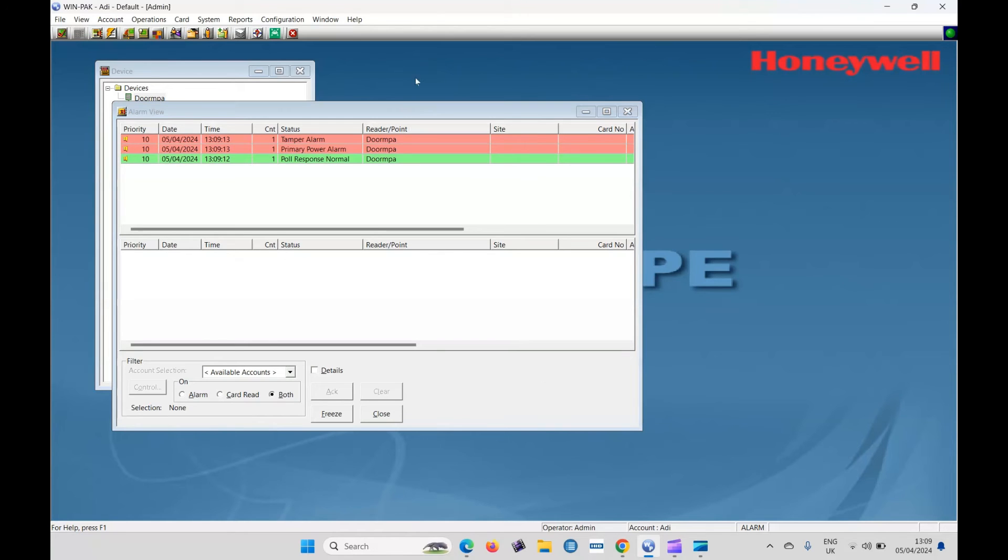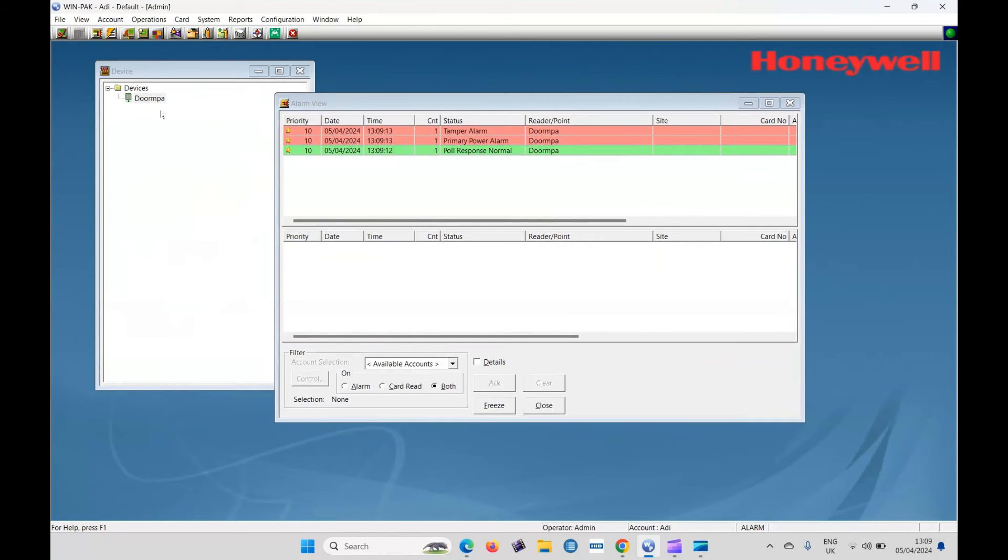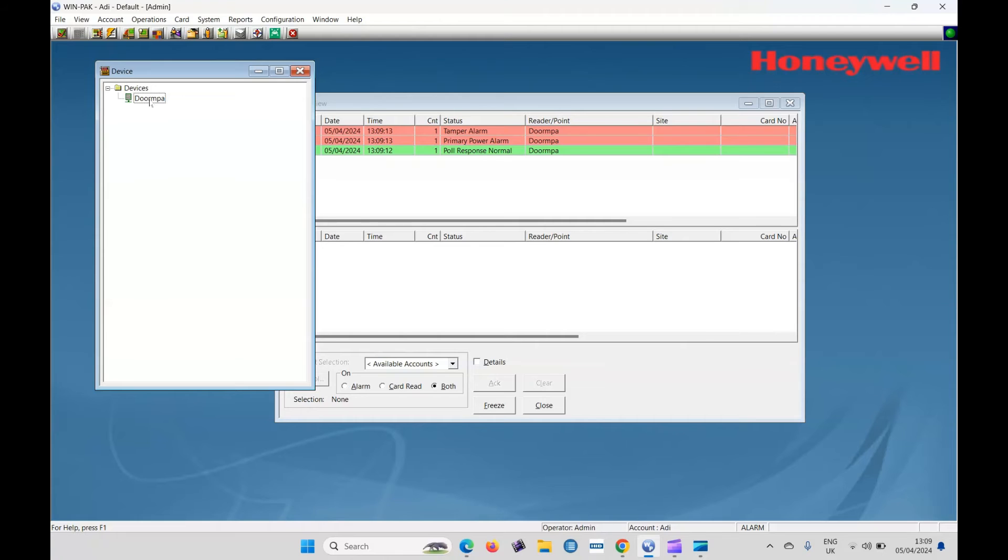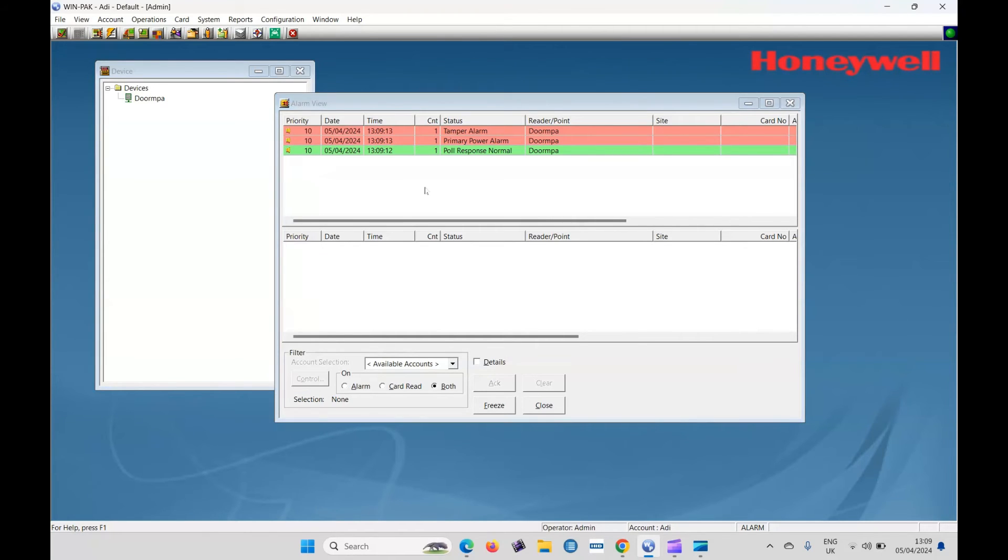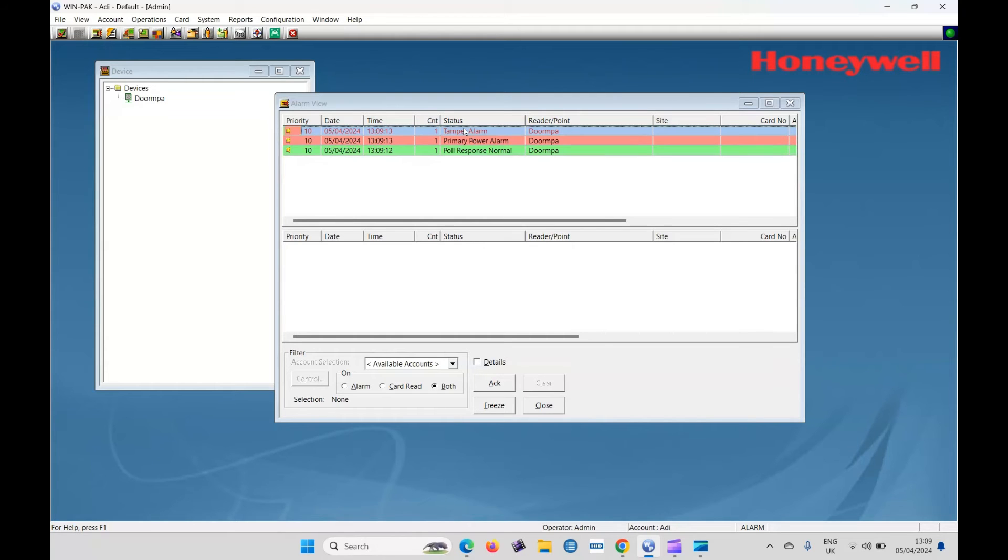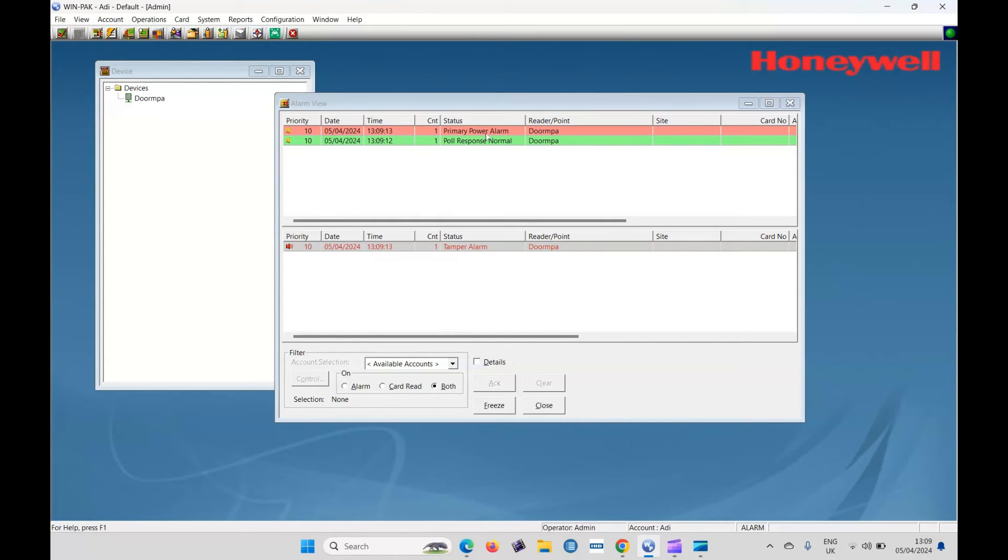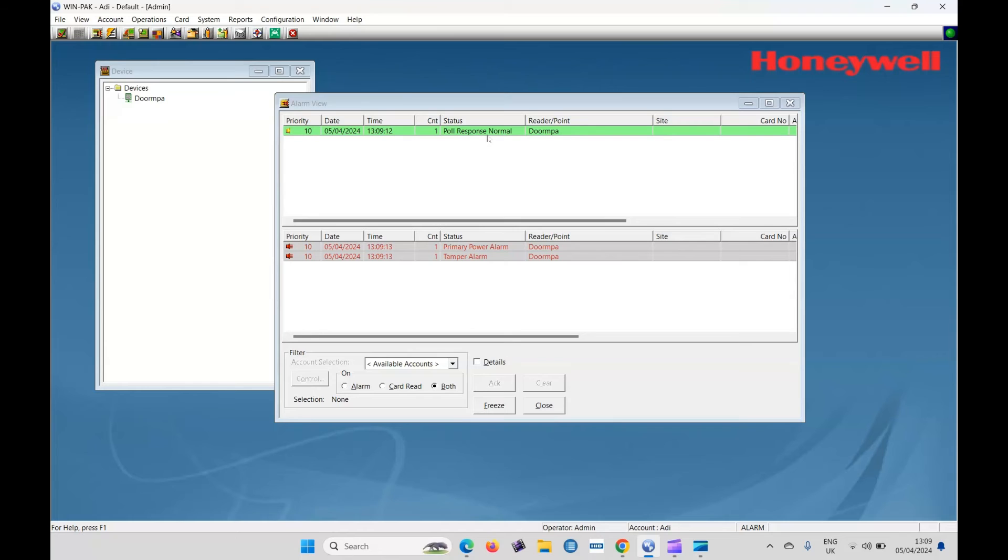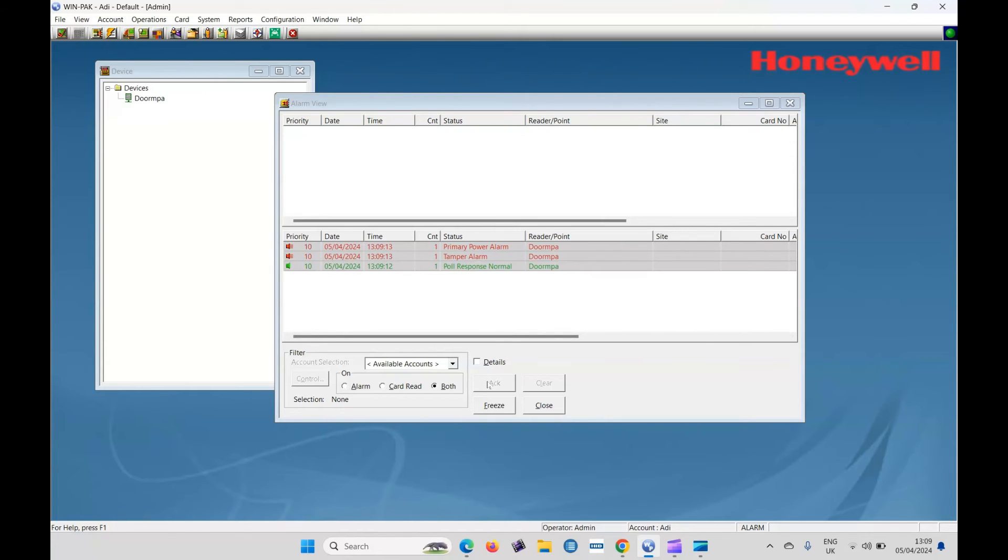Oh, there we are. So in the device map here, you can see the doors come up. It's now added to the suite in the alarm window. It's come up with a couple of alarms. First of all, it's the green saying the door is online. The poll response is normal. That's good. Power, primary power is down. Well, that's true because mine's POE. And I've not put that link in. I've not told it is POE only, and the lid is open. So they're all fine and we can ack those alarms to acknowledge them and they might reoccur later on. So that's the door added and confirmed that it's added to Winpak.